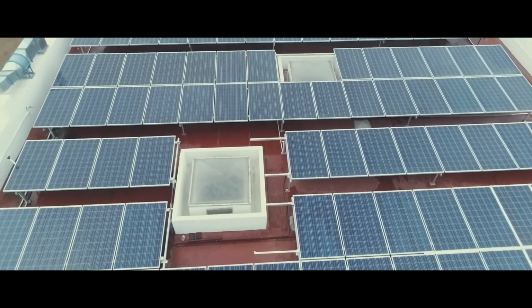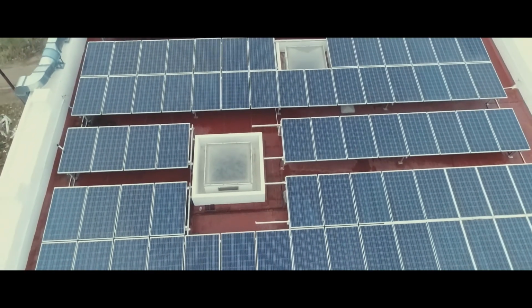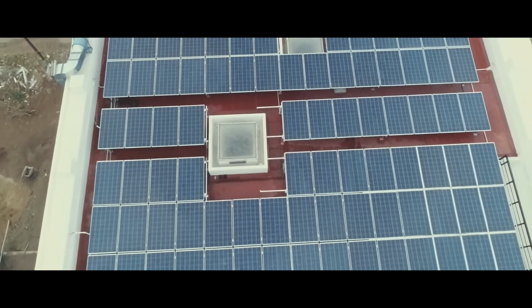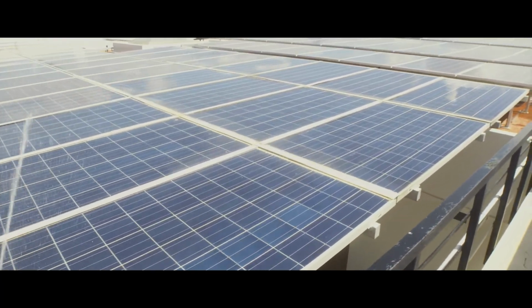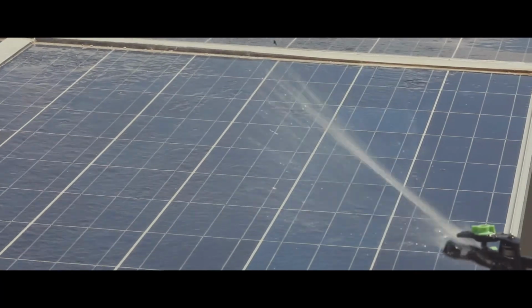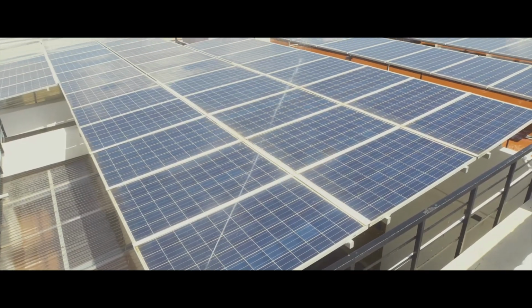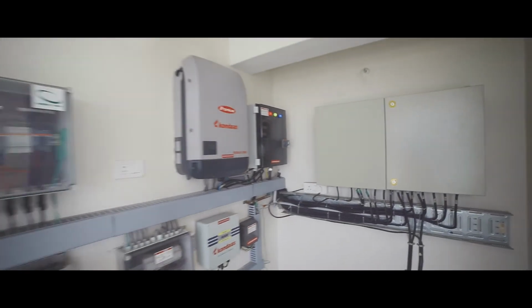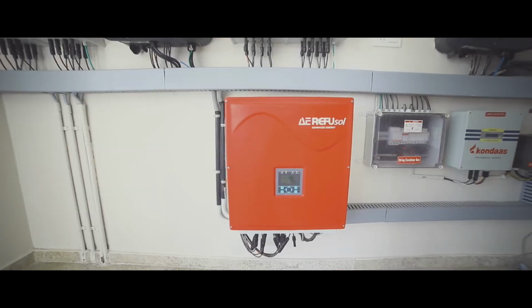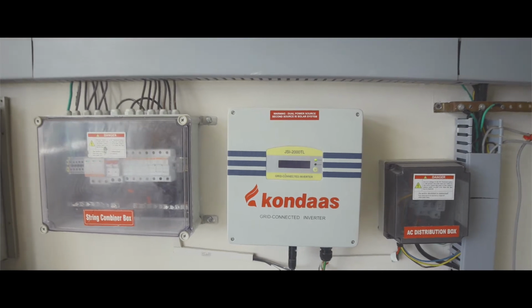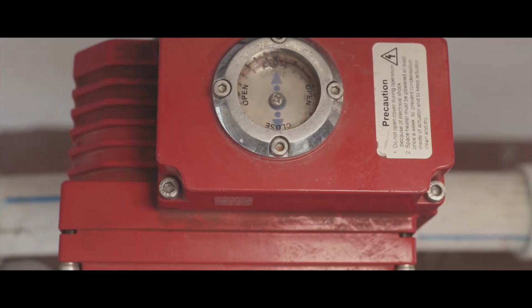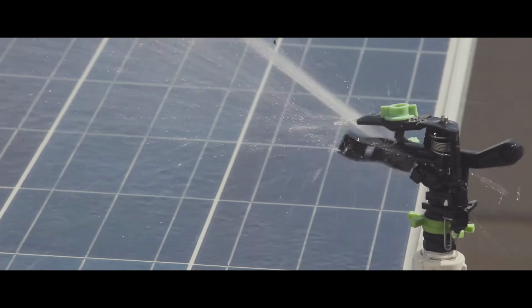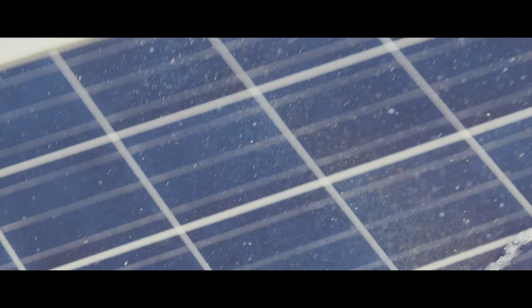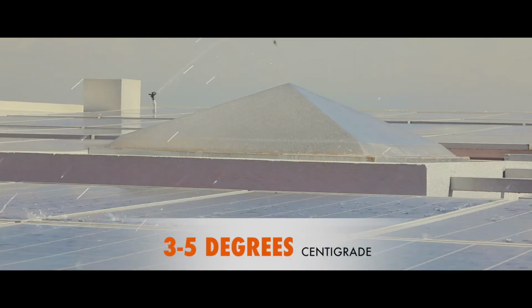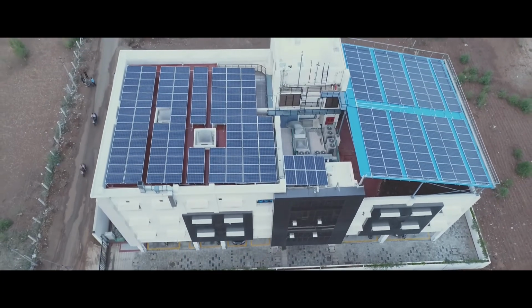Solar panels lose efficiency with every rise in temperature above 25 degrees centigrade. Sierra has implemented a unique system to cool the panels. Real-time irradiation and solar panel temperature detectors provide data to the building automation system. Using this data, the building automation system activates automated valves to spray small amounts of water. This reduces the panel temperature by about 3 to 5 degrees centigrade and keeps the panels dust-free.